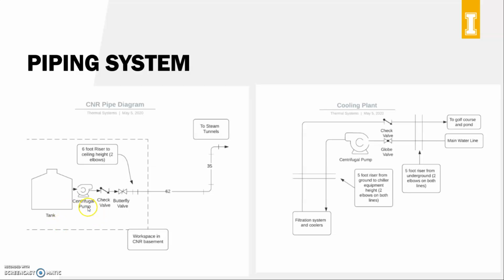floor. Now, next, the water flow will go into this centrifugal pump, and I'll talk more about this pump later on one of our other slides. And then next it goes into this check valve, and this check valve is actually really important because if we're pumping all this water up a long distance in a pipe system all the way up the hill, and this pump were to suddenly shut off or fail, then all that water would start rushing back down the hillside and would probably blow through the pump, might blow up the tank, and could even flood the CNR basement. So this check valve is really vital to be at the very bottom of the water system.